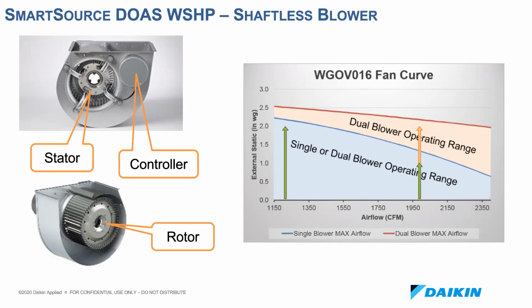If you need 2 inches of static at the same 2000 CFM point, you would need to pick the dual blower option. Because of these EC motors, we have developed both constant volume and variable air volume control sequences. For constant volume applications, you will simply program the airflow you want and the fan speed will self-adjust. Our VAV options are covered in more detail in a different presentation.